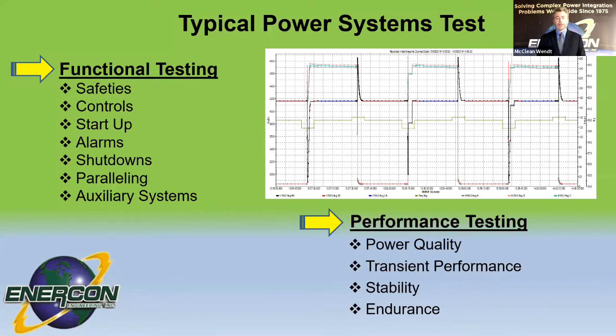And we'll start it. Sometimes we'll start in idle and make sure that everything's spinning the correct way. And if we can, test to make sure that everything is being sensed correctly. And then we'll move into rated. So the engine will start spinning at 1800 RPMs, typically for a 60 hertz unit.